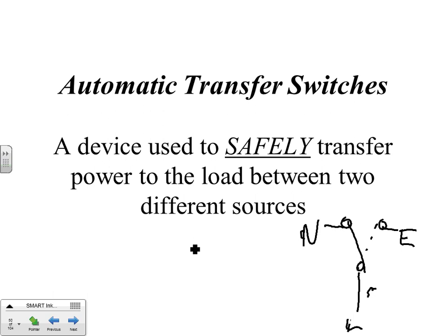There's voltage sensors in here. It starts the generator set, and when it comes up to speed and frequency, the sensors here see it, and they transfer this, and it transfers over in this way, effectively opening that circuit to the utility. The other problem that was created when somebody tried to do it handyman style, when they backfeed that panel, that's actually going out to the pole. And if you've got a lineman that's trying to fix the problem in an outage, you could knock him right off the pole because it'll work as a step-up transformer going in reverse. So anyway, it'll safely transfer the power.